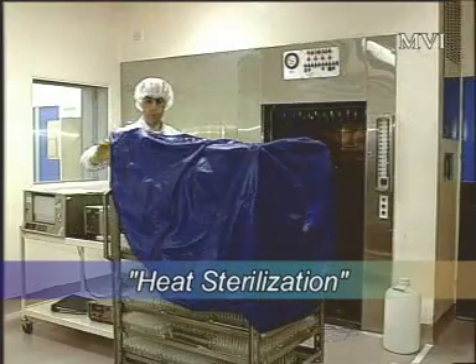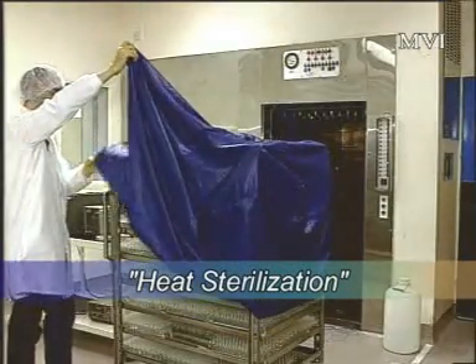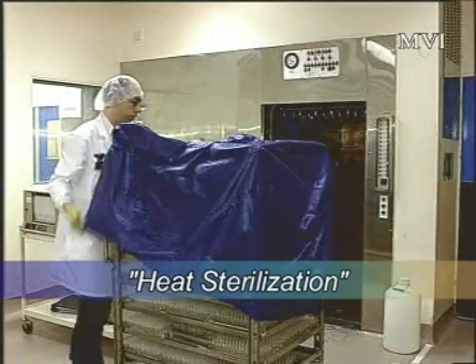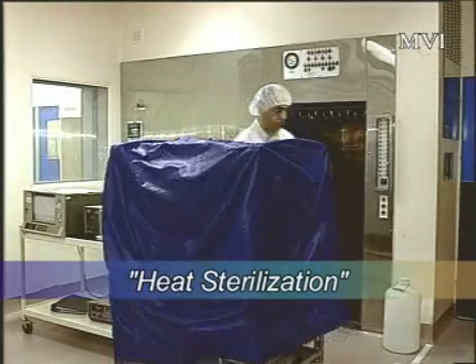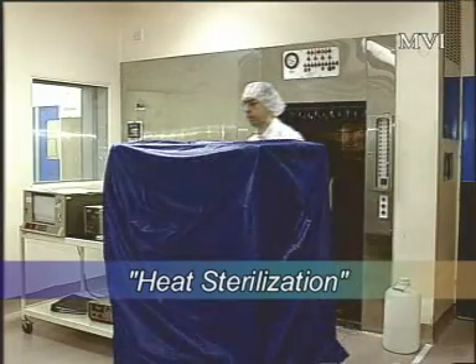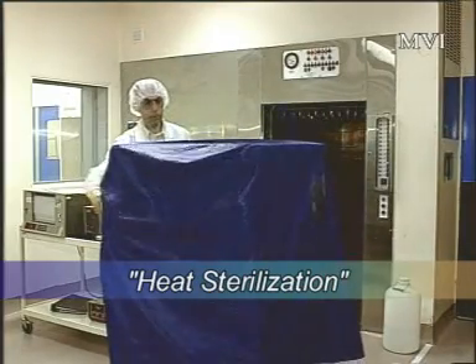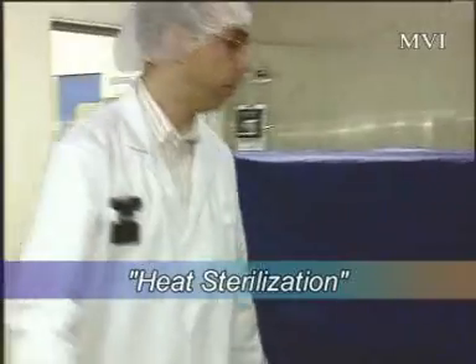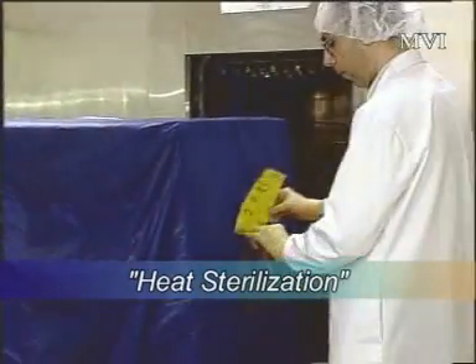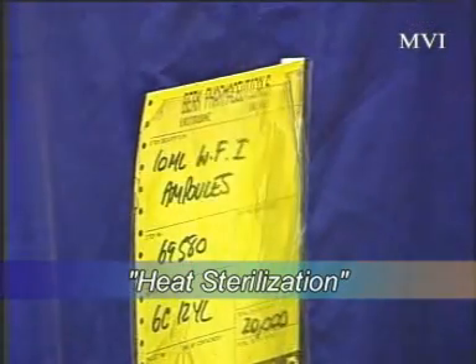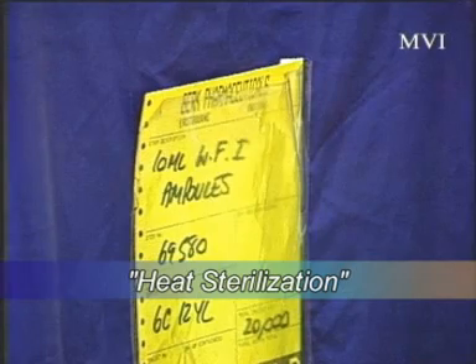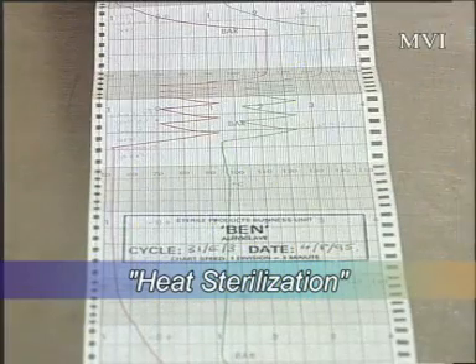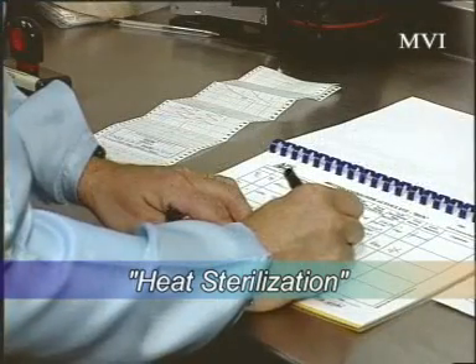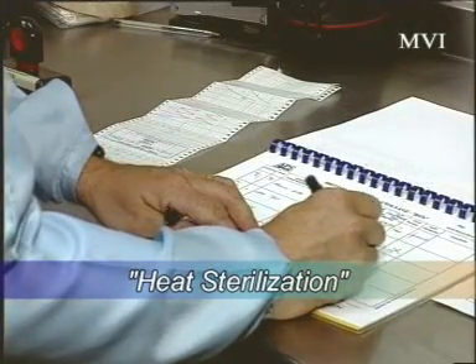An unambiguous way of differentiating between loads which have reached the minimum conditions and have been successfully sterilized and those which have not. Every tray, basket or carrier, together with each individual product or component, must be clearly identified with the product or material name. The chart that this produces at the end of each cycle is the principal record of the sterilization, and either the original or a photocopy must form part of the batch production record.